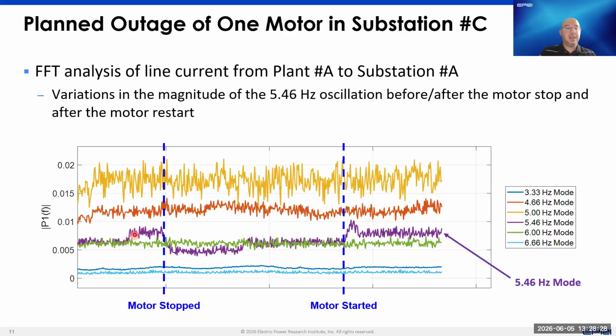Then it increases, and what we suspect is happening here, because this was a planned outage, is that the load customer, in anticipation of one of the motors being stopped, increased the loading of the other motor, basically to compensate for the production. So before the motor stopped, you see that the energy increased. Again, we suspect that the industrial customer increased the loading on another motor. Then here was the plant outage, or the motor stop, and you see a significant decrease in the energy of that oscillation mode, which can be explained by the fact that the motor stopped.